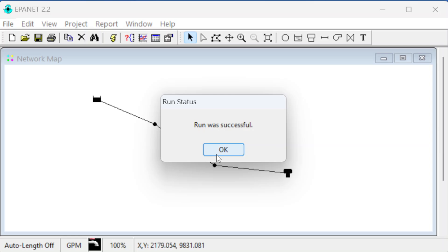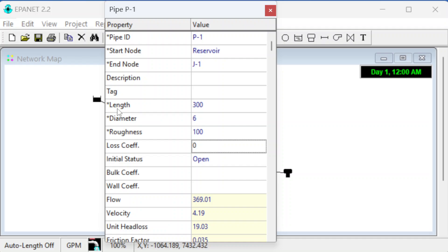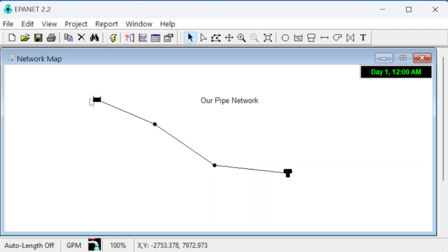Let's go ahead and run it. It says the run was successful. If you get problems, an error message can help you figure out if you left off a pipe diameter or set it to zero. Now we can pull up the information — clicking individual pipes shows the computed flow rate. This first pipe shows 369 gallons per minute, and the second shows 269, which makes sense because 369 minus 100 pulled out at J1 equals 269.